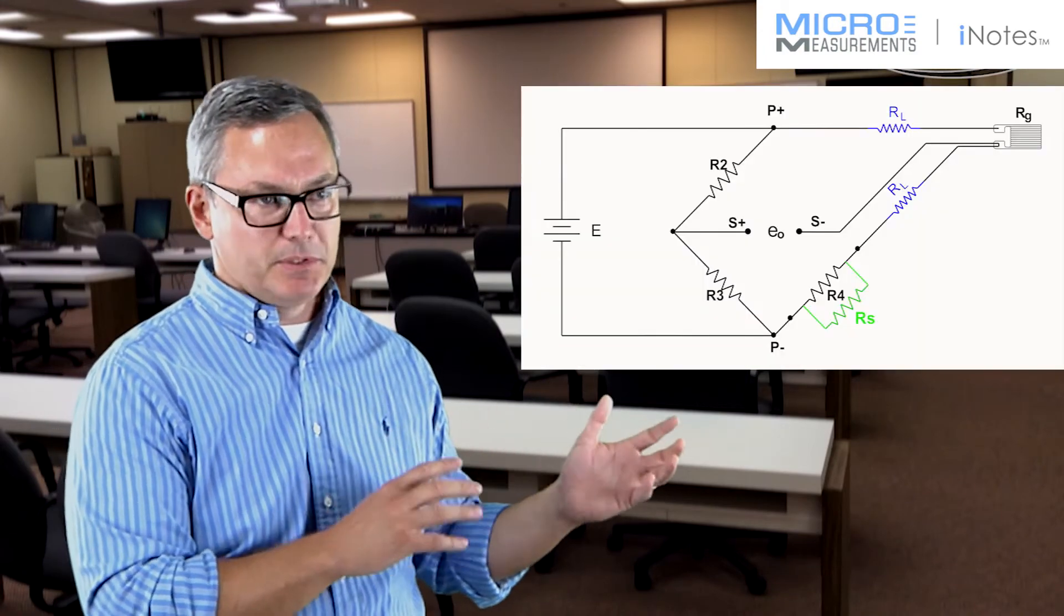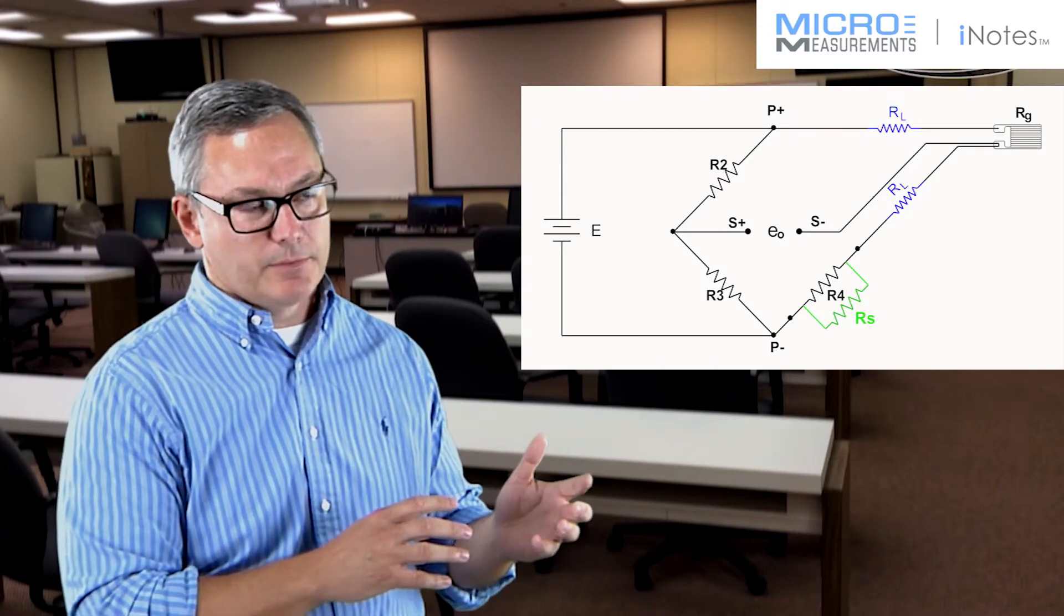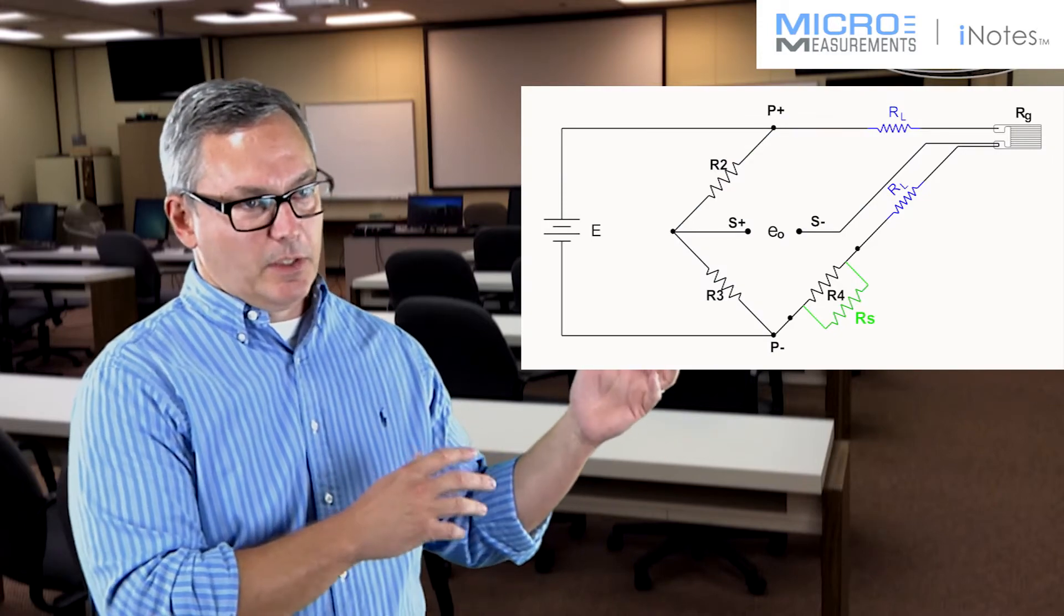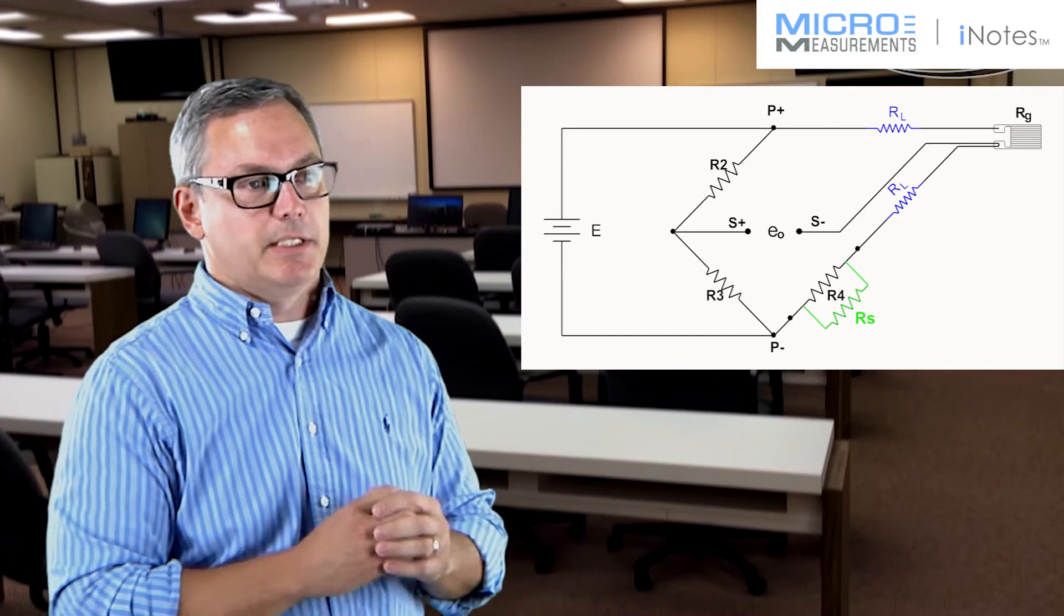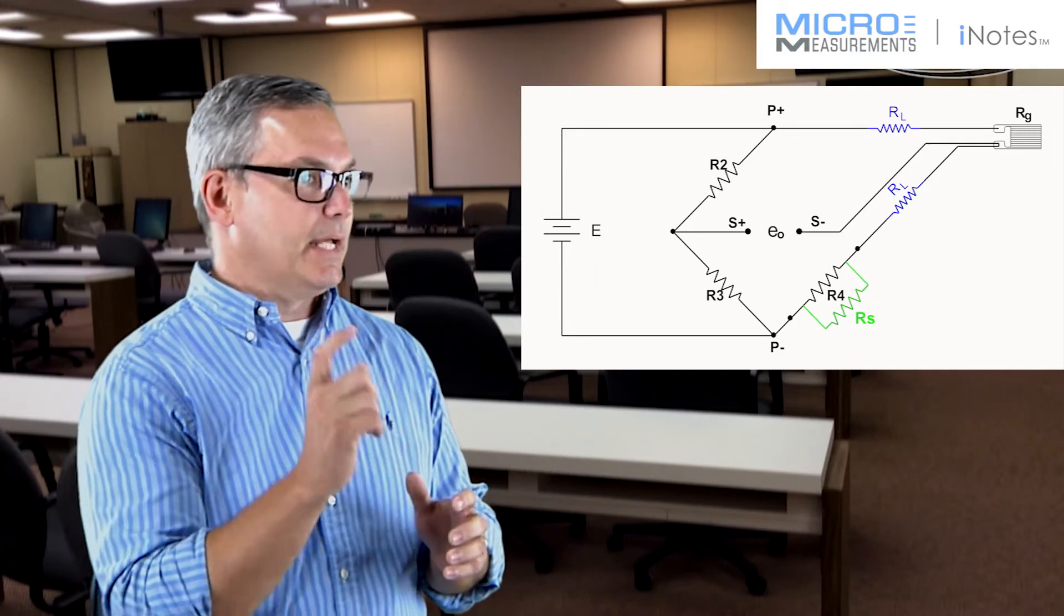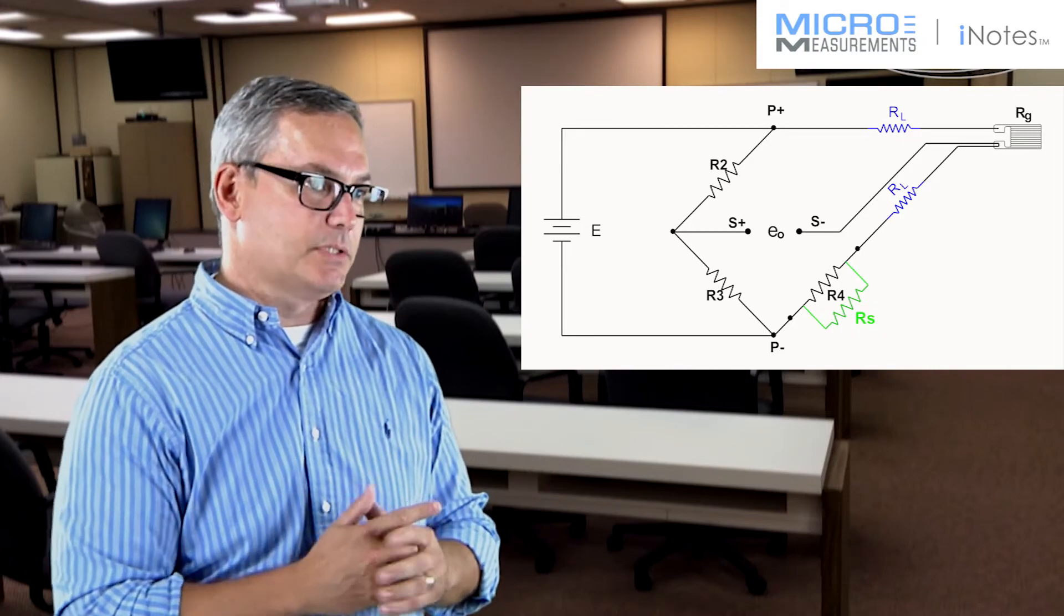Now, with our own instrumentation, specifically our data acquisition, we like to shunt calibrate across what's known as the dummy resistor in the Wheatstone bridge. If you take a look at this sketch, you'll see that this resistor gets connected across the resistor that has to match the input resistance of your strain gauge.